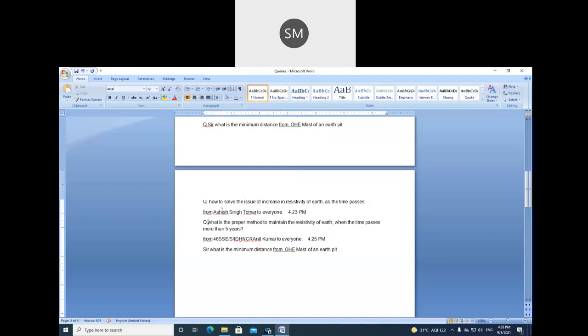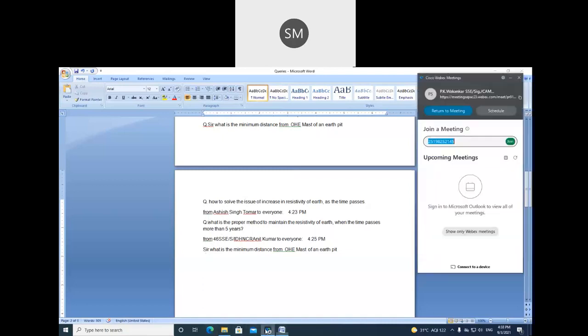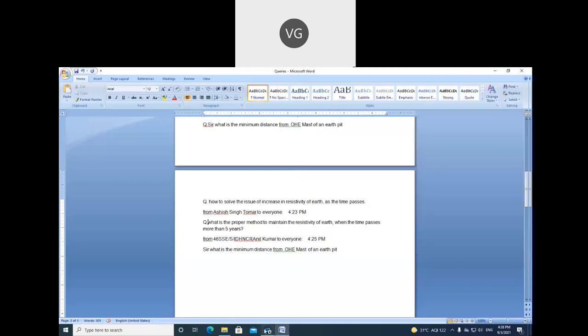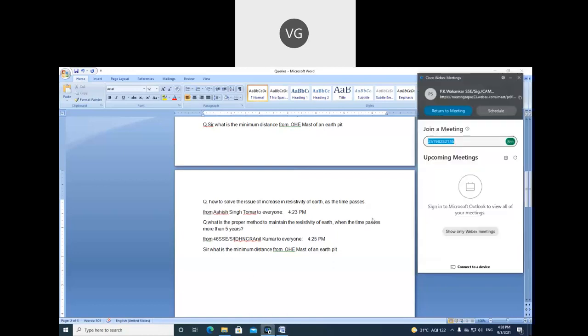Anyway, if there are any more questions, please forward them to me. There is one question from Mr. Ravi Shankar Mishra: what is the standard method of earth resistance measurement? Well, you can sometimes use a clamp-on meter to measure the resistance value of the earth pit or the grid. This is the fastest method. You can either isolate it, or there are megas available now which can measure the individual earth pit without disconnecting it to get the earth pit resistance value, and we are going to purchase one very soon.